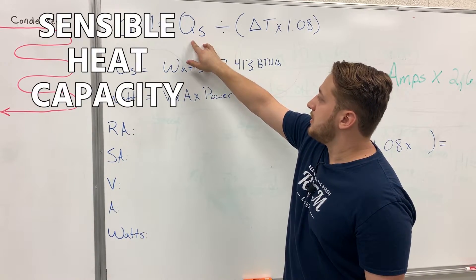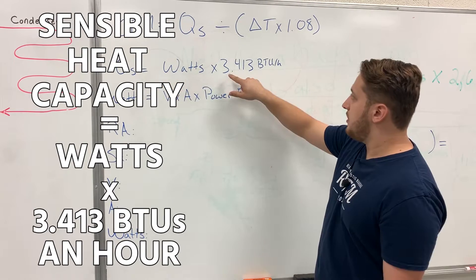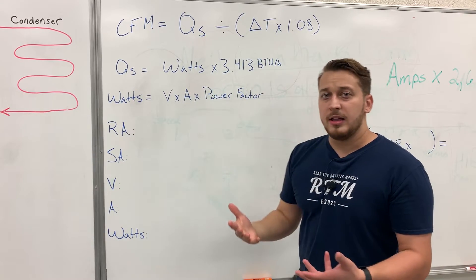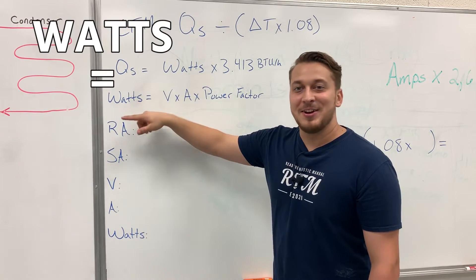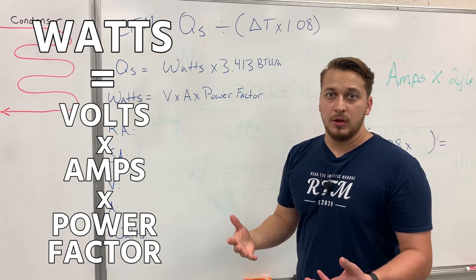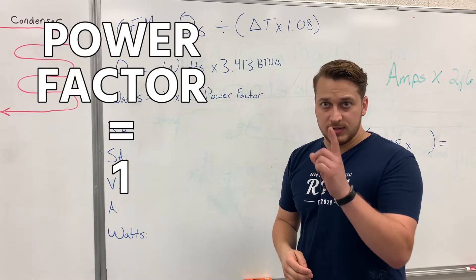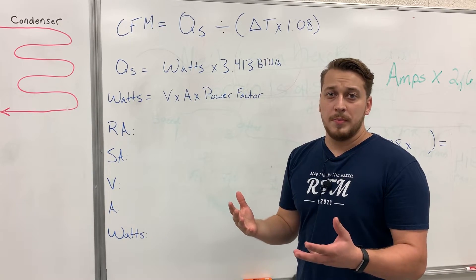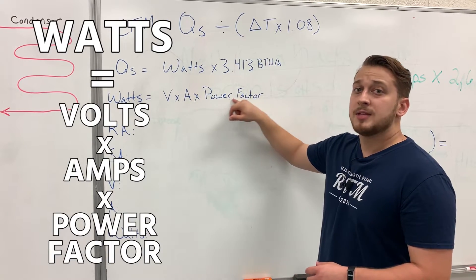To calculate sensible heat capacity, it's watts times 3.413 BTUs per hour, since there are 3.413 BTUs in one watt. To calculate watts, we're using electric heat — a resistive load. The formula is volts times amps times power factor. Because it's resistive and not inductive, there's no reactive power, so the power factor equals one (unity). We'll keep it in the formula to remain precise: watts equals volts times amps times power factor.